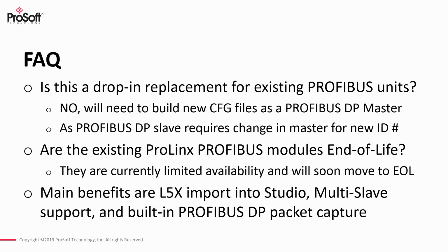And then to wrap up, the main benefits are really the L5X import into the Studio 5000 environment, the ability to operate as a multi-slave device on a PROFIBUS network, and that PROFIBUS DP packet capture utility. From some of the installations that I've worked on, any kind of advanced diagnostics always required third-party hardware, and so being able to do this in one hardware module definitely speeds up installation and commissioning time, and really makes things a lot easier for people that are implementing it.